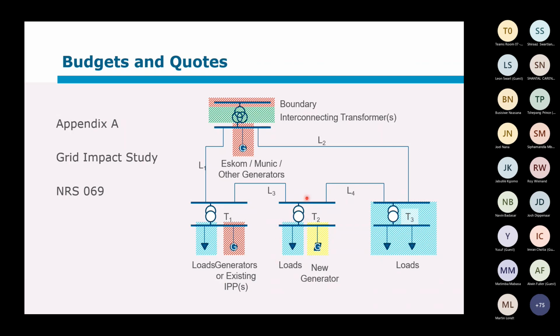Okay, so obviously, if you add transformers, you need more bays. Well, maybe there is a spare bay, but let's assume you don't have one. So that might actually mean extension of the bus bars. It might mean additional bays. The same for the lines. You're going to need one extra bay for the transformer on this bus bar here, one for the line.